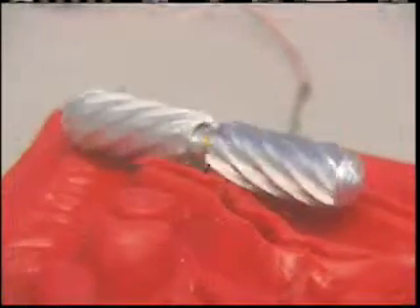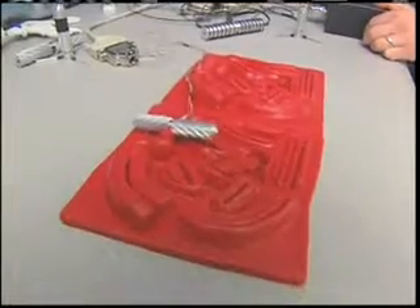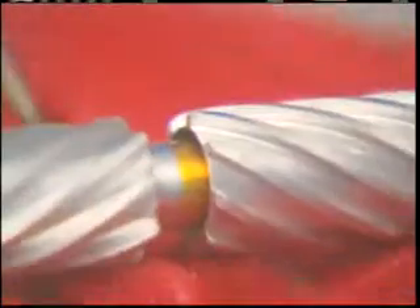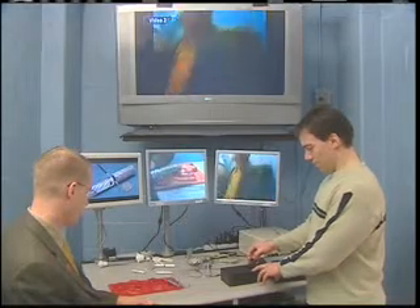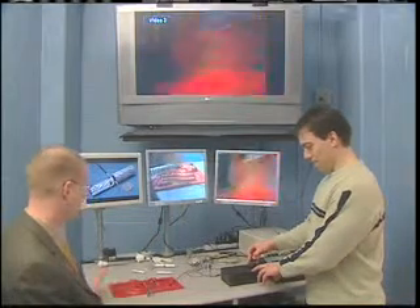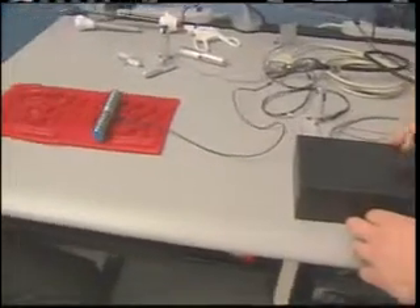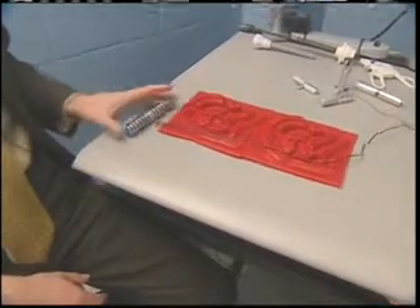Although the test robots are wired, they'll eventually be wireless. But putting wireless capabilities inside the robot means making it bigger. Power is a problem — if a robot is in a remote environment like that, it has to provide its own power, so you need space for batteries. Transmitting video is also challenging, and surgeons demand really high-quality video. And then there's getting commands into the robot itself — you want a low-power receiver, which is a challenge as well.